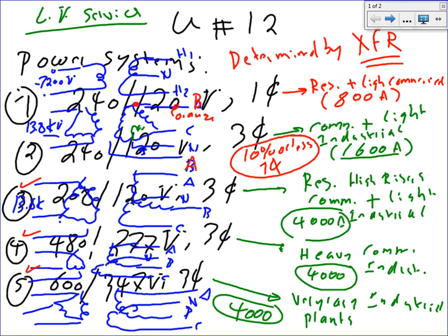Let's look at 3. 3 is on the primary side, 13.8. I care less about the primary. Most of the time I put the 13.8 for you because that's what we'll mostly get in the cities here. I have no control over it. On the secondary side, that's my baby. I get 208/120 on the secondary side, a 3-phase system. Where would I pick a system like this? If you have residential high-rises or an apartment building, that's a good system to pick, 3-phase. Commercial plus light industrial is a good application for 208/120, like the project that we guys have.